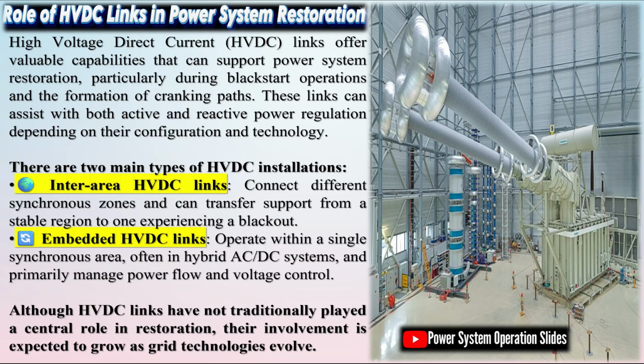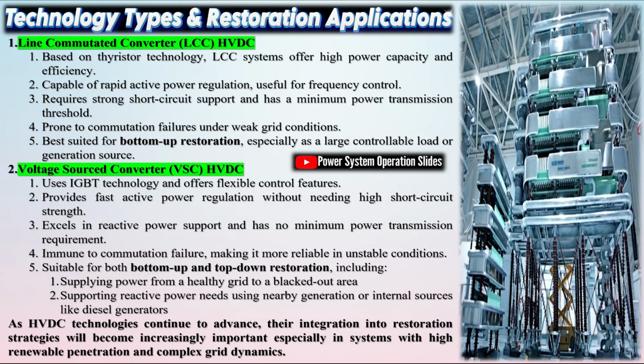Line commutated converter (LCC) HVDC. Based on thyristor technology, LCC systems offer high power capacity and efficiency. Capable of rapid active power regulation, useful for frequency control. Requires strong short circuit support and has a minimum power transmission threshold. Prone to commutation failures under weak grid conditions. Best suited for bottom-up restoration, especially as a large controllable load or generation source. Voltage-sourced converter (VSC) HVDC uses IGBT technology and offers flexible control features.